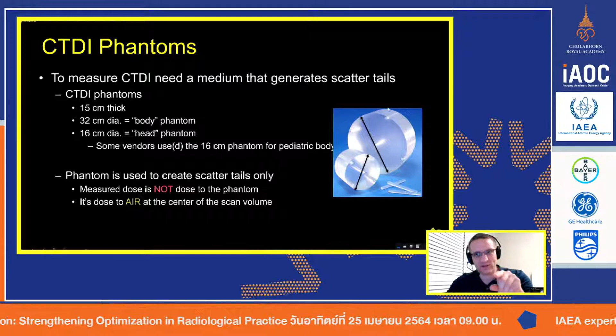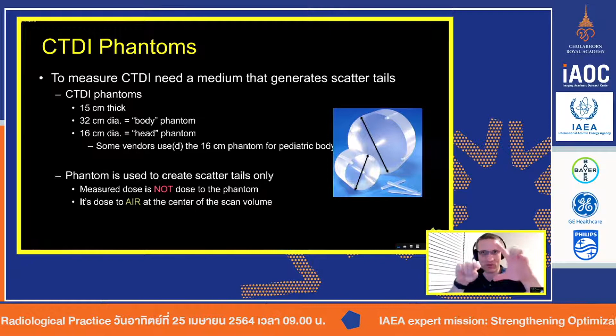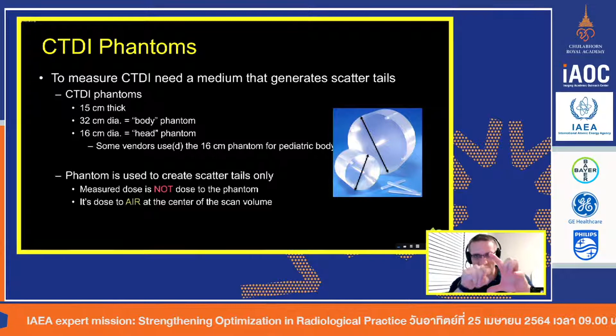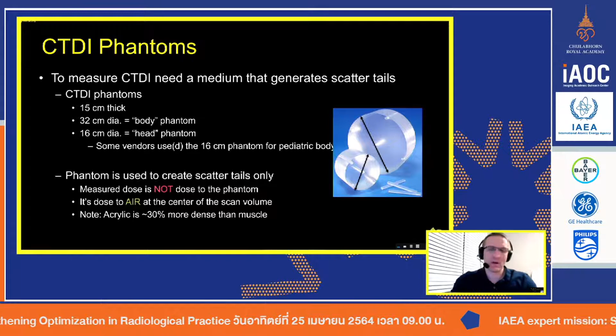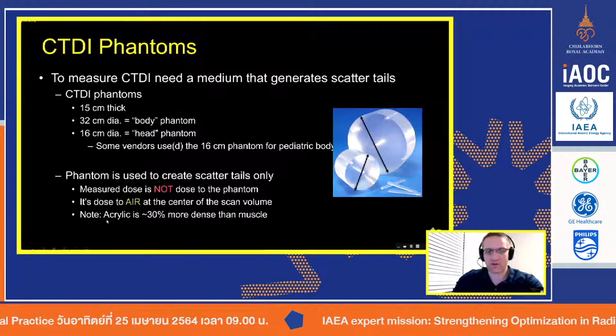Even though we'll make some measurements around the periphery, it's actually the dose to the center. So when you think of a CT scanner, the bore, you have isocenter right in the middle. The CTDI value, that value that you see on your CT console, represents dose to the air in the center of the CT scanner if there was scatter from a patient body. And things to understand, these phantoms are made out of acrylic, so they are actually about 30-something percent more dense than muscle. So obviously they're going to attenuate differently than our bodies.